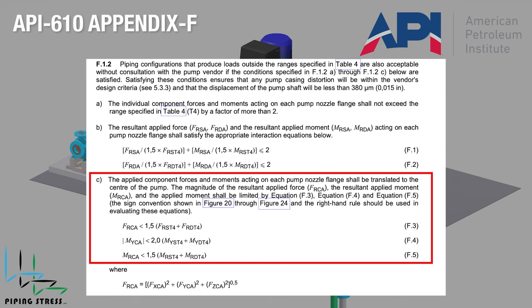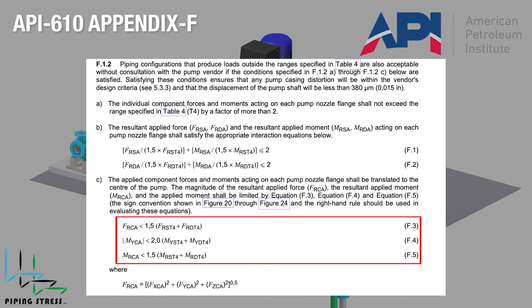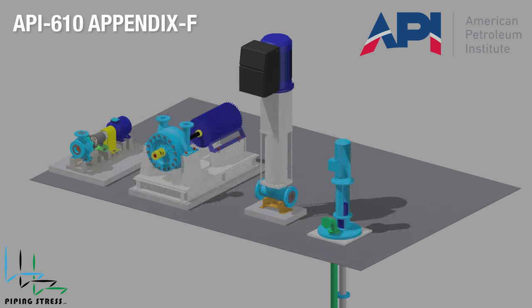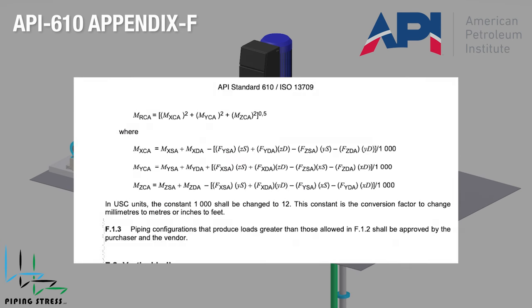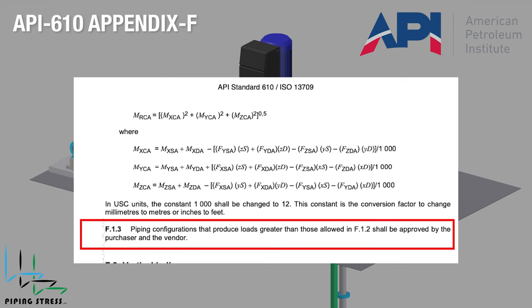The magnitude of the resultant applied force, moment, and the applied moment shall be limited by equations F3, F4, and F5. Finally, F1.3 states that piping configurations producing loads greater than those allowed in F1.2 shall be mutually approved by the purchaser and vendor.